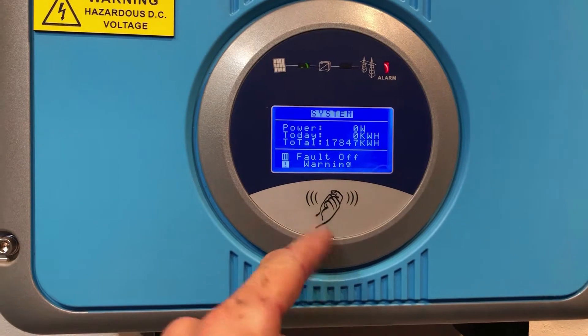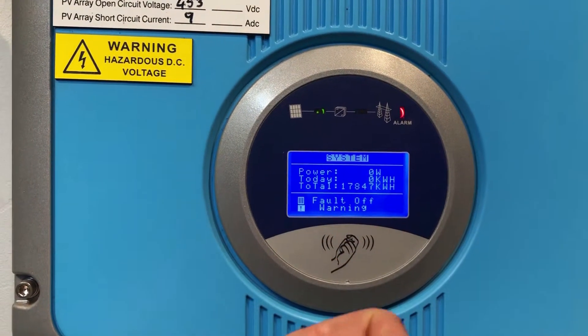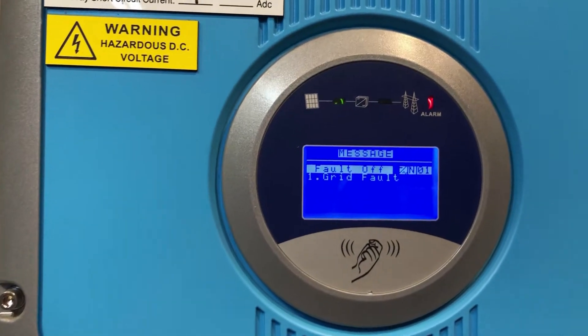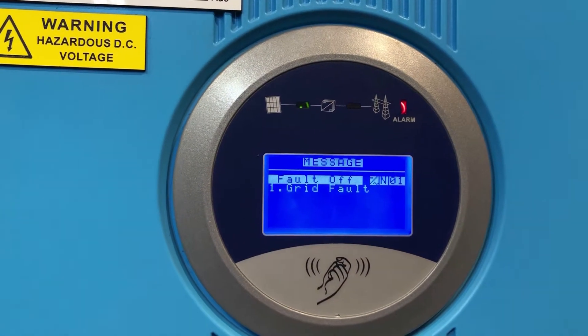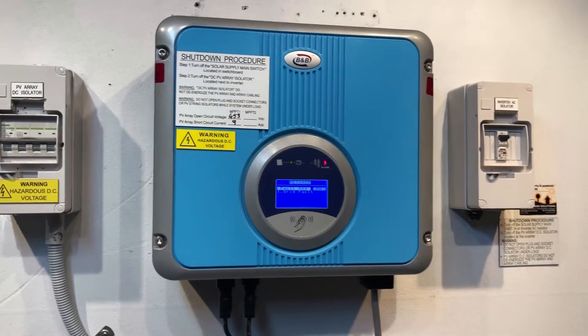Now if you see here, there's a picture of a knock on the screen. With B&B inverters, if you knock on or near the screen like so, it should go through the different readings. You can see here it's coming up with a fault message which is saying 'grid fault'.